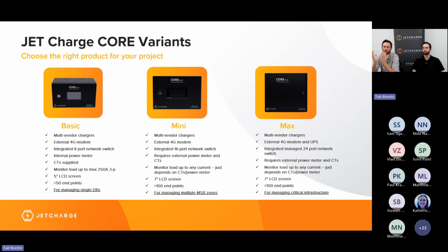For example, you might want to install a power meter on the site supply and on the car park power supply so that Core can monitor and calculate the spare capacity at both points. Because of this, you're free to select the CTs best suited to your project, meaning there isn't a limit on the load you can monitor, unlike with Core Basic.